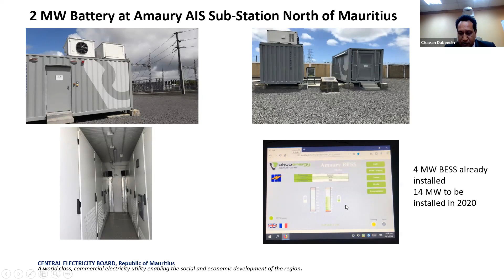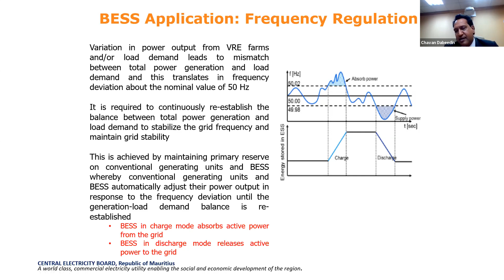So what happens is that when they are set, for example, at 50.02 and 49.98, when the frequency is above 50.02, the battery will be charged. And when the frequency is 49.98, the battery will discharge in the bus bar, will discharge on the grid to provide the power, to compensate, to correct the frequency.